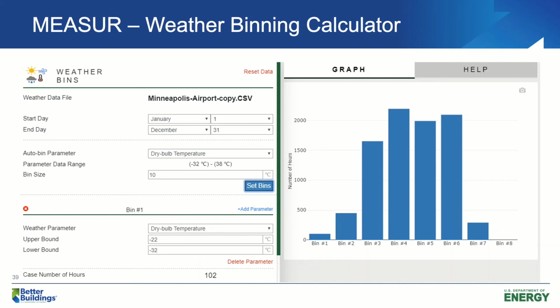You only need to upload the weather file and to tell the calculator which weather range you are interested in. This calculator will tell you for how many hours a year the temperature is within that range. That number will be your operating hours savings.